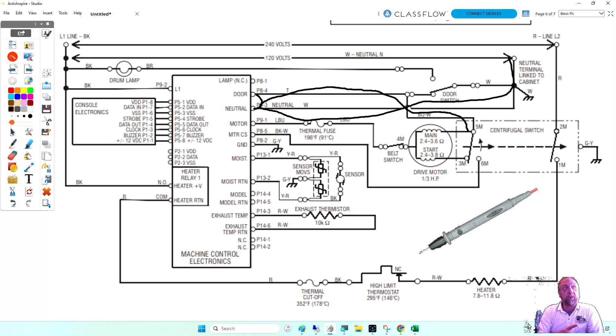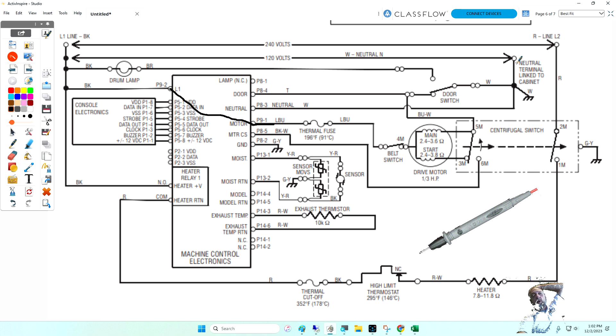If I jump out the relay 91, 92, I don't have to press start because I'm bypassing the relay, which is what says start. But if I don't press start - this just kicked in my head real quick - if I jump this out, I don't have to press start because I'm sending power directly to my motor and it goes right out neutral. But what won't happen is I won't see this work if I just jump this and don't press start.